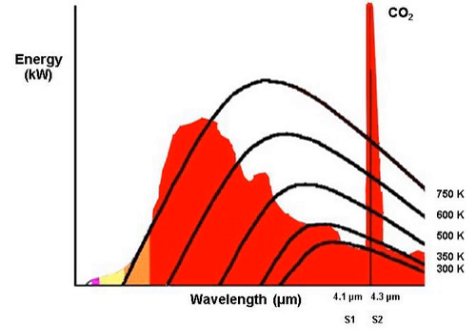A severe disadvantage is that almost all radiation can be absorbed by water or water vapor. This is particularly valid for infrared flame detection in the 4.3 to 4.4 micrometers region. From approximately 3.5 micrometers and higher, the absorption by water or ice is practically 100%. This makes infrared sensors for use in outdoor applications very unresponsive to fires. The biggest problem is our ignorance.